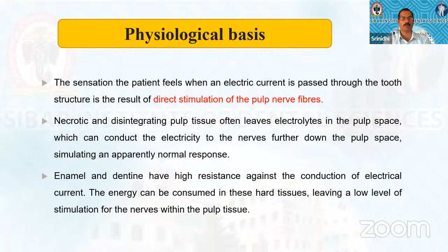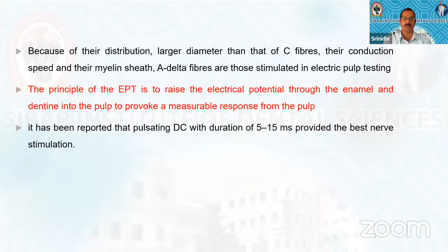And one more important factor is the thickness of the enamel and dentin, and this may provide some amount of resistance to the passage of current. So C fibers are the last to get stimulated. A-delta fibers are the ones which are stimulated by the electrical testing. And the principle is to raise the electrical potential through the enamel and dentin to provoke a measurable response from the pulp. And the direct current, which has been pulsated with a duration of 5 to 15 milliseconds, is the best stimulation for the testing.